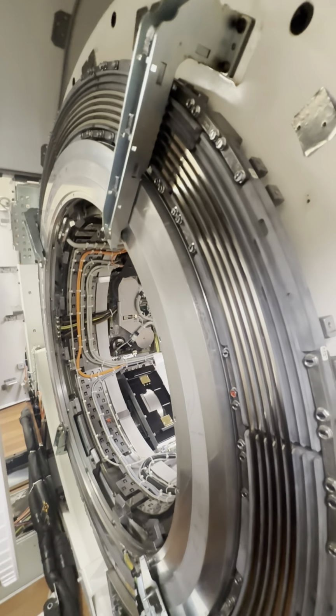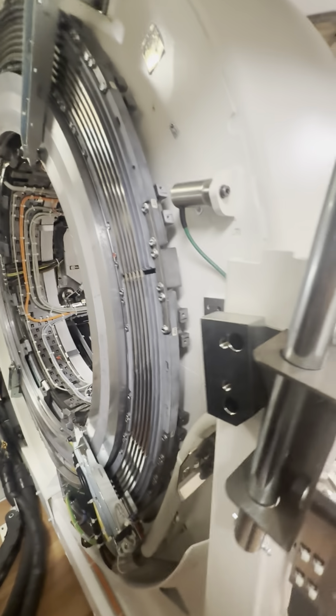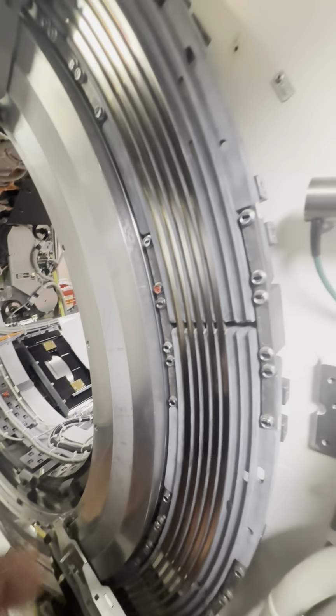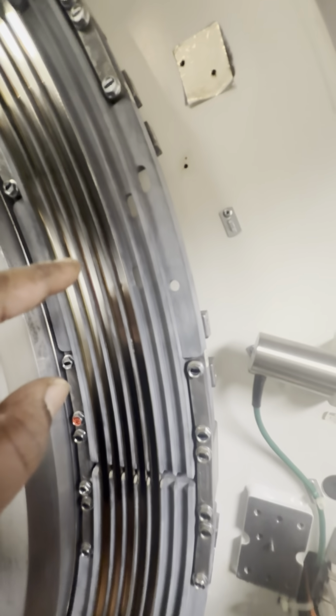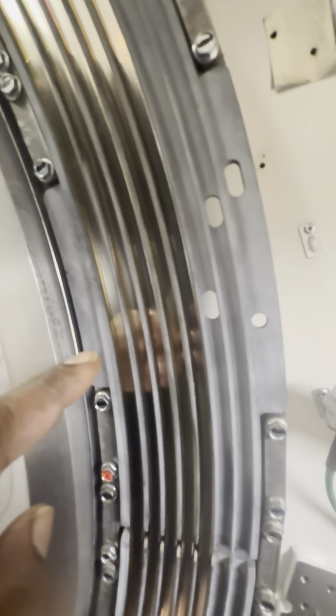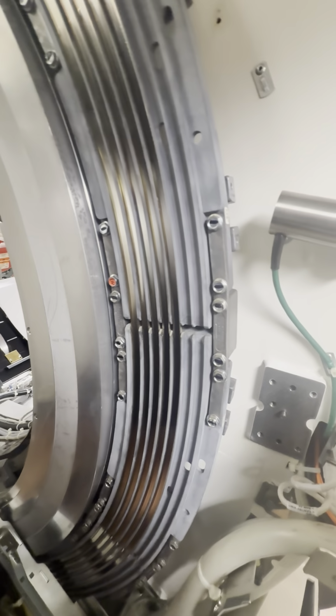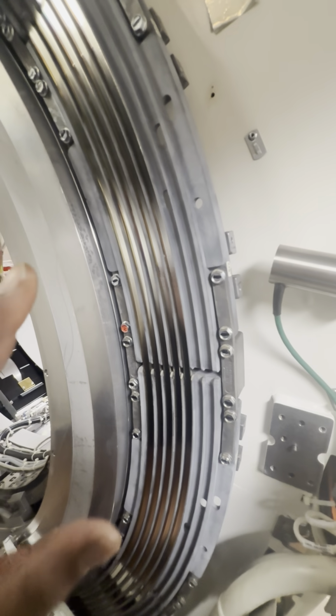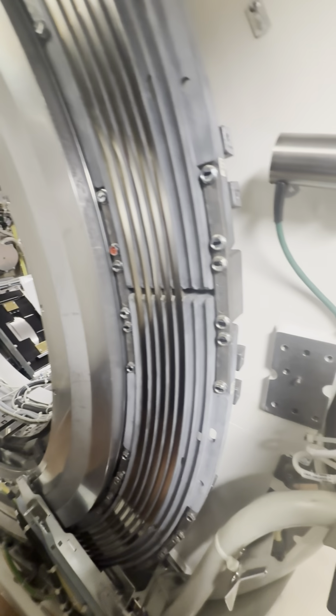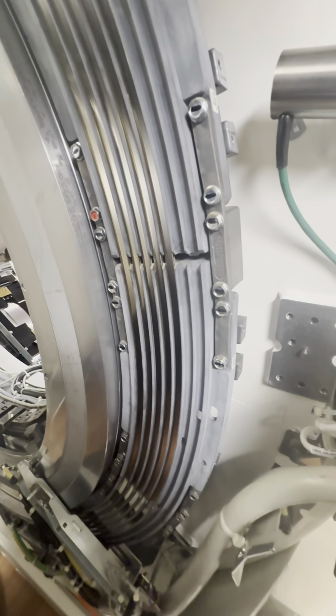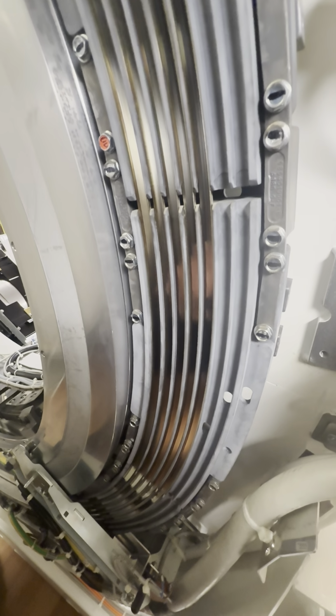All right, so here is the rear of the CT. This right here is something you need to be very concerned about if you're working on the system. This is your slip ring. This right here, which is the bus block, is where all the power goes in and out. The major power. We're talking about 430 volts AC across most of these rings except for the neutral and ground. So these first three should be about 430 volts AC, and you shouldn't be touching the slip ring at all with your hands or even with gloves, or you can say goodbye. All right, that's why we get paid what we get paid, because there's a lot of danger.